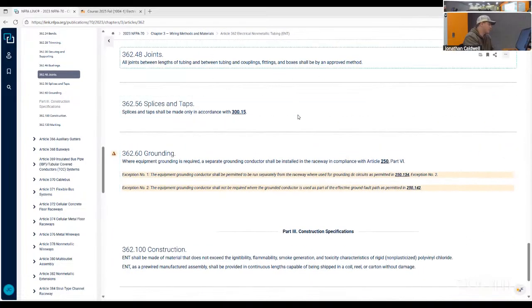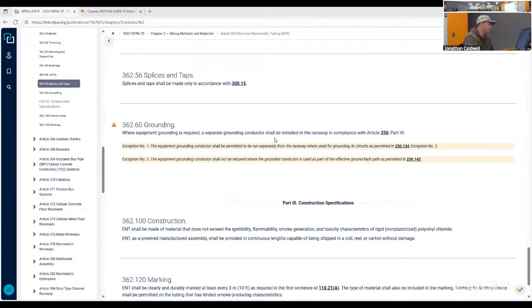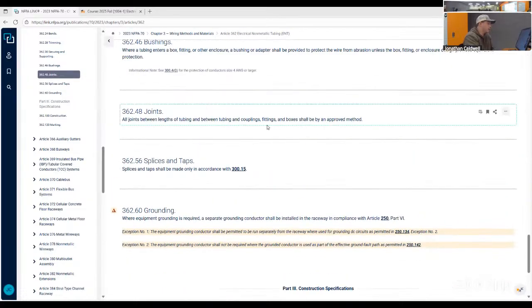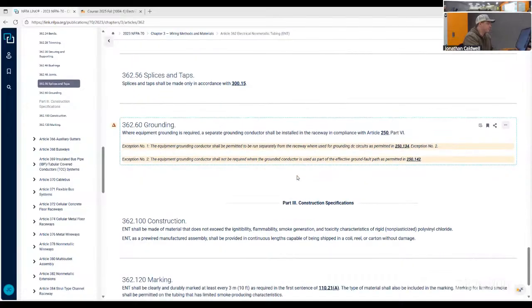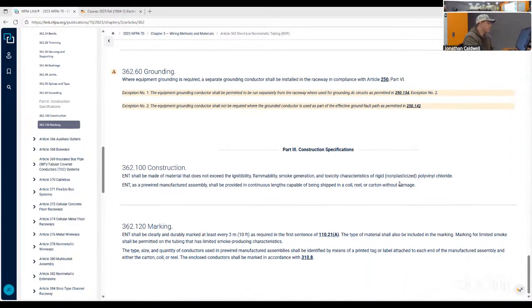And then all joints have to be couplings, or you have to use the appropriate fittings for that. You can't just Smurf tube right into a plastic box. It just doesn't work that way, unless the plastic box is ready for it and it's marked. And there are different types of ENT you can buy. Just like with PVC conduit and things like that, they have different ratings. And that's all this last one was talking about, so.